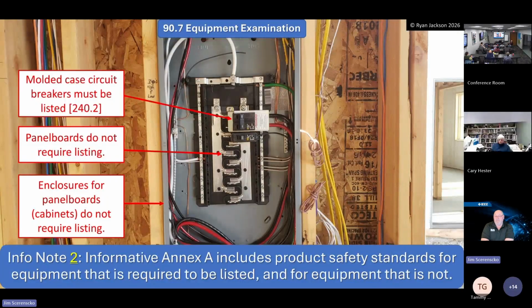So whether it's built to a standard that they keep at the factory and they don't have to stamp it as being listed, I don't know, to be honest. Or if it's a component that they build that goes inside the enclosure, I don't know. But the breaker can be used in any panel board, whether it's listed or not. So maybe it's because it's a separate component, sold separately and installed separately. That's why it's got a separate listing on it.